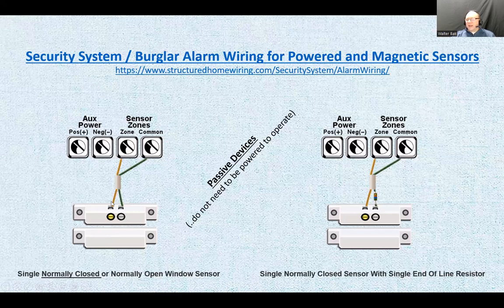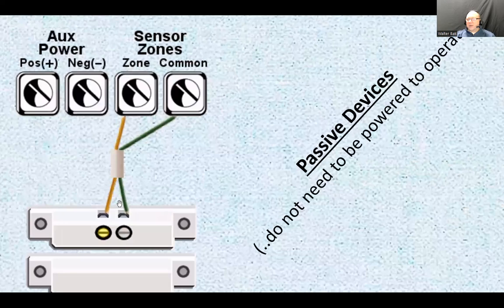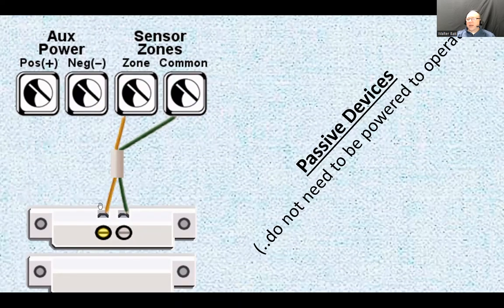And you see, over here, we're using that yellow and green. For the most part, the green will be connected to the common terminal of the zone, and the yellow will be connected to the signal. However, because it is just a free hanging, not attached, dry connection, if you reverse those, it's not going to make a difference. However, just to make things nice and consistent, for the most part, you're going to see this type of stuff.